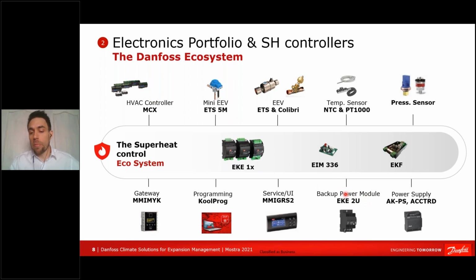You have a power backup module. This one, EKE2U, using capacitors, helps you close the valve properly when you have a failure of the chiller. You don't want the chiller or your compressor to be flooded when you have a failure. You want the valve to close properly to avoid any slug in your compressor when you start again after you fix the failure. So this backup power module ensures that the system is closed properly when you have a failure.